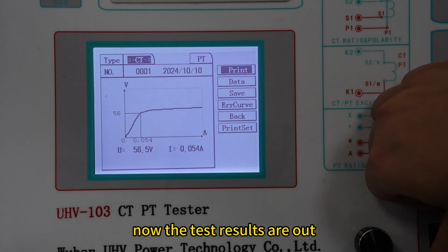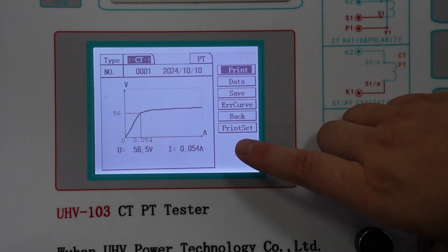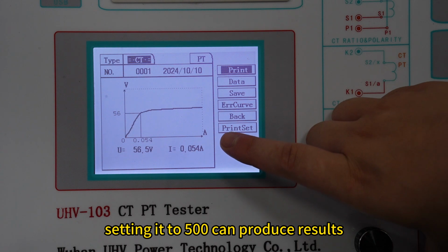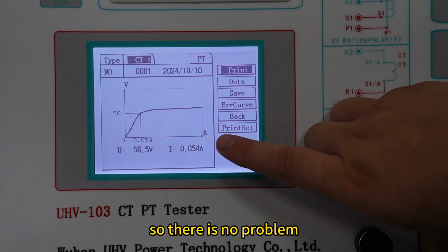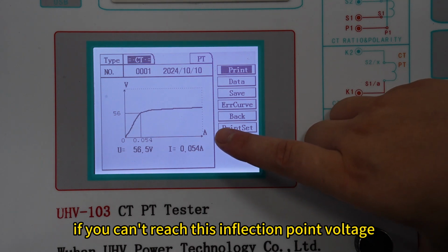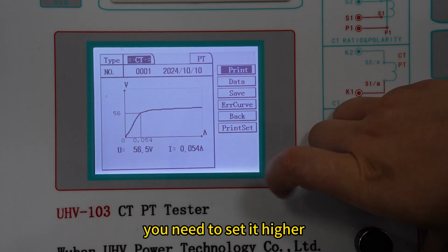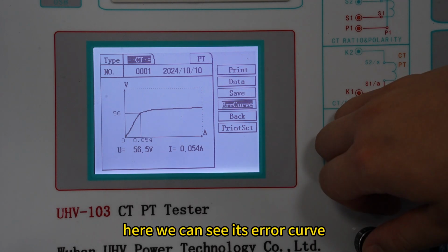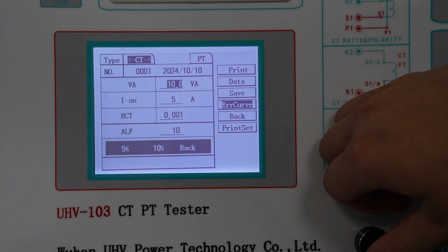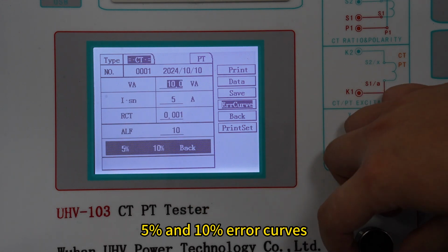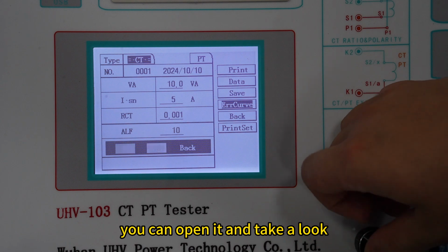Now the test results are out. Setting it to 500 can produce results, so there is no problem. If you can't reach this inflection point voltage, you need to set it higher. Here we can see its error curve. 5% and 10% error curves. You can open it and take a look.